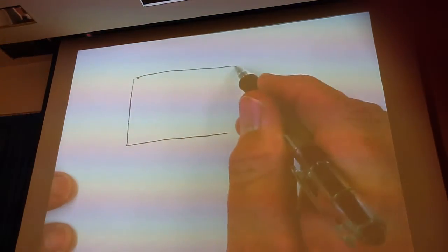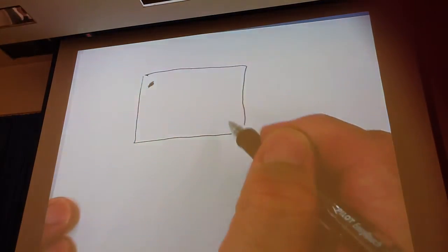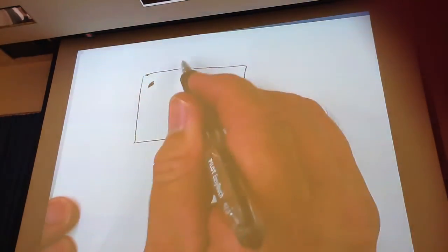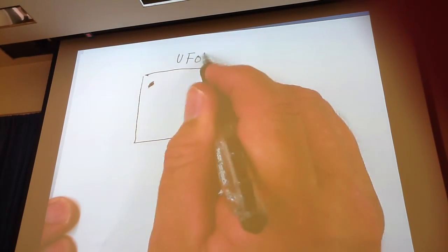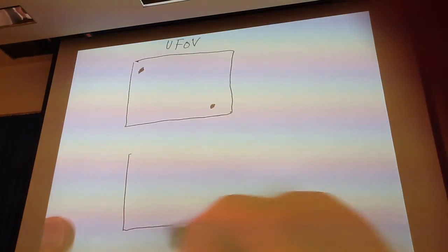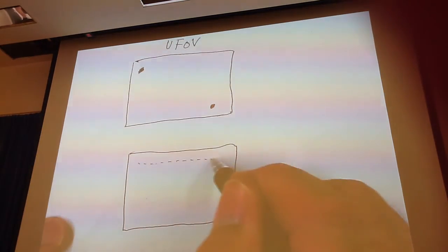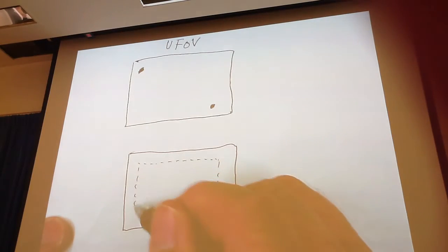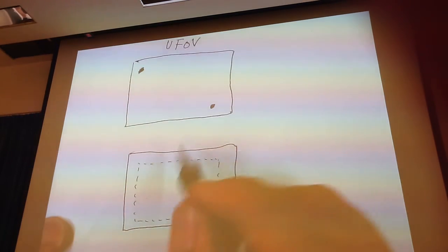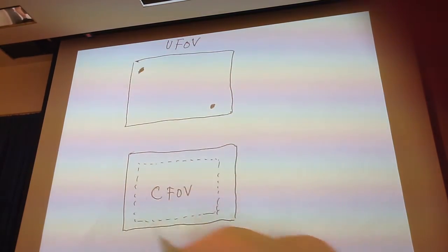Okay, so the differential, the whole count, the integral. The integral, I could have a hot spot here and a cold spot here, anywhere in the useful field of view. Okay, and they don't have to be adjacent to each other. Okay, remember the differential. First of all, it's only going to involve the central field of view. And that always is 80% of the useful field of view.